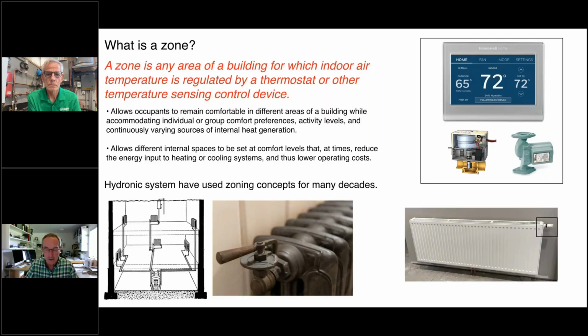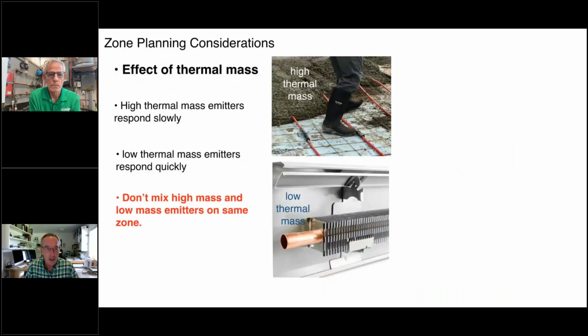For example, internal heat gains might push the temperature up. That valve will reduce the flow rate under that condition and maintain a fairly accurate, let's say plus or minus 1 degree Fahrenheit of set point. And again, we're going to get into that type of zoning as well. So what are planning considerations for zones? One of them is thermal mass. And I've got a couple examples here of a radiant slab, 4 inches of concrete, 6 inches of concrete, very high thermal mass. So it's going to have slow response characteristics.